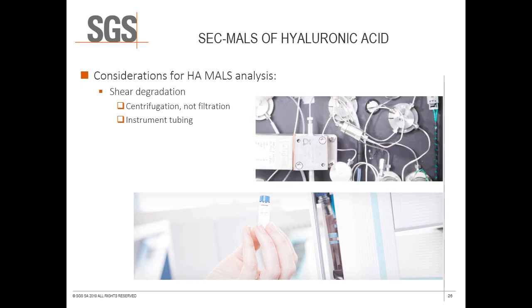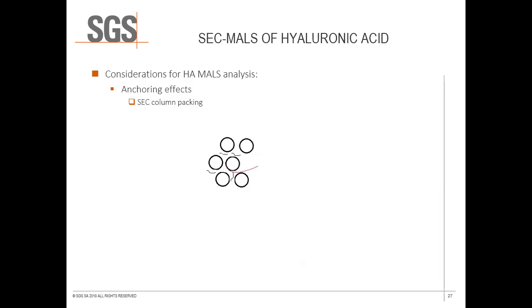Tubing with an internal diameter of less than 0.01 inches should not be used for SEC systems characterizing high molar mass species. SEC columns must be chosen which will allow the polymer molecules to separate adequately, but do not put molecules under great levels of shear stress. Columns with large packing particle sizes are recommended not only to reduce shear, but also to reduce anchoring effects. Anchoring refers to polymer chains eluting later than expected due to their great size and their difficulty passing freely through the column packing, as shown by the theoretical red polymer molecule here.